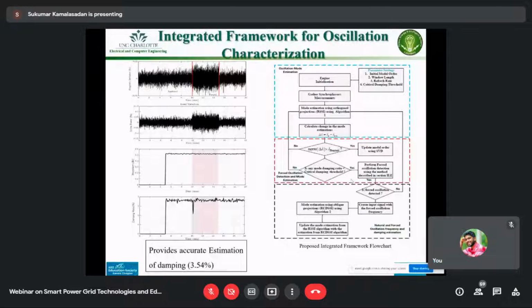So what do we do with these oscillations? The first thing is to characterize them, and determine whether they are coming from within the power grid or external to it. This example shows the modes of oscillation, the damping percentage, and whether the oscillation is coming internally or externally.